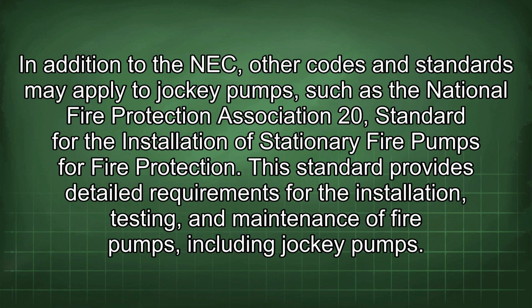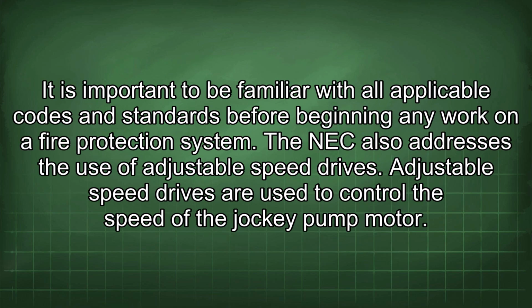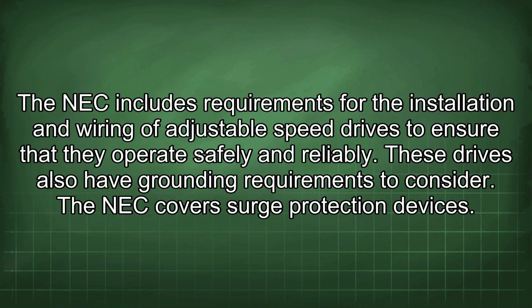This standard provides detailed requirements for the installation, testing, and maintenance of fire pumps, including jockey pumps. It is important to be familiar with all applicable codes and standards before beginning any work on a fire protection system. The NEC also addresses the use of adjustable speed drives. Adjustable speed drives are used to control the speed of the jockey pump motor. The NEC includes requirements for the installation and wiring of adjustable speed drives to ensure that they operate safely and reliably. These drives also have grounding requirements to consider.